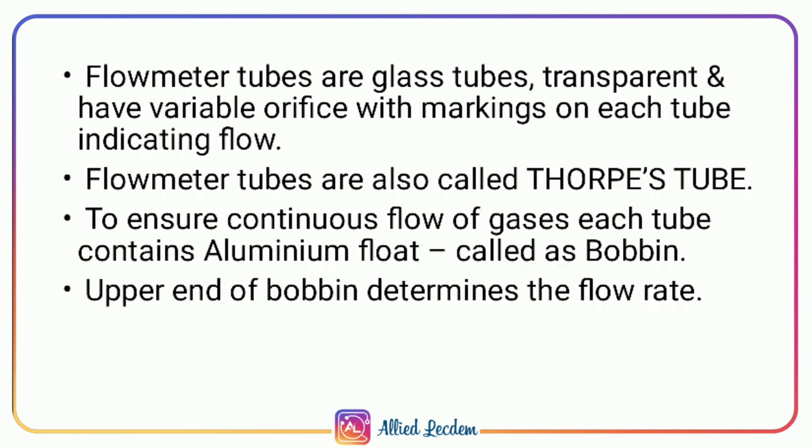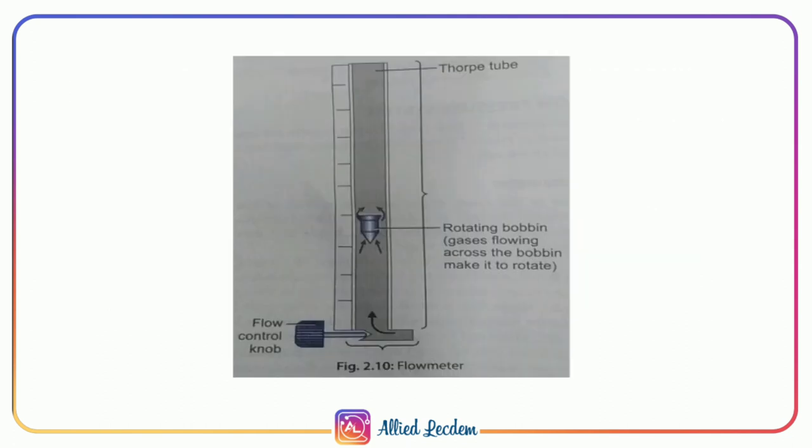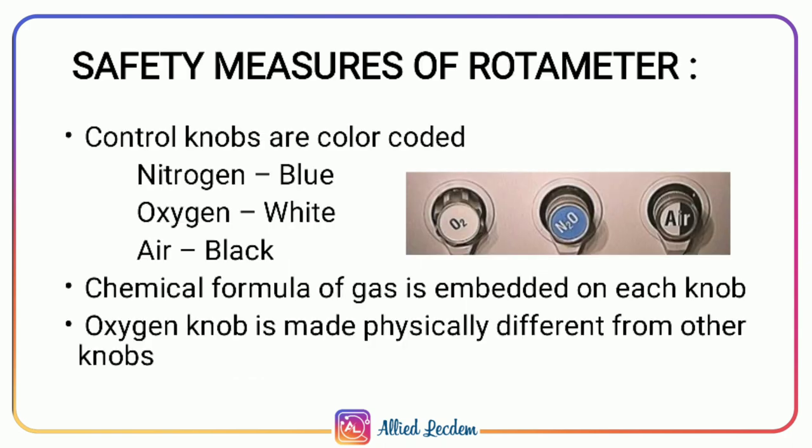The flowmeter tubes are glass transparent tubes with various markings indicating flow, also called Thorpe's tubes. To ensure continuous flow of gases, each tube contains bobbins made up of aluminium — the upper end of the bobbin determines the flow rate. When there is gas flow, the bobbin rotates and floats at the specific set level.